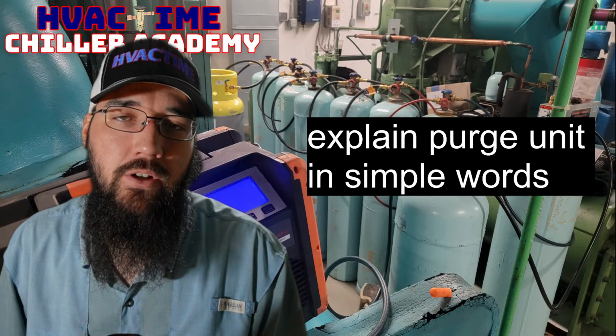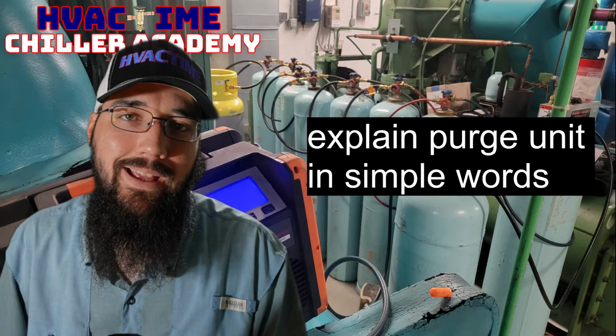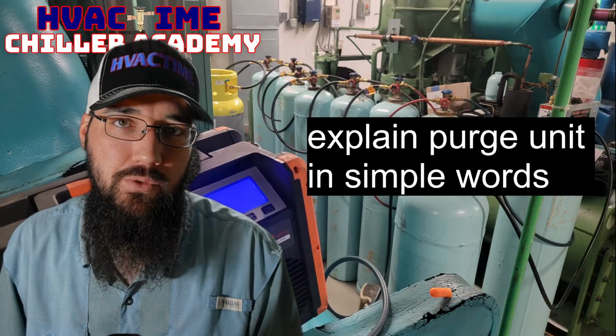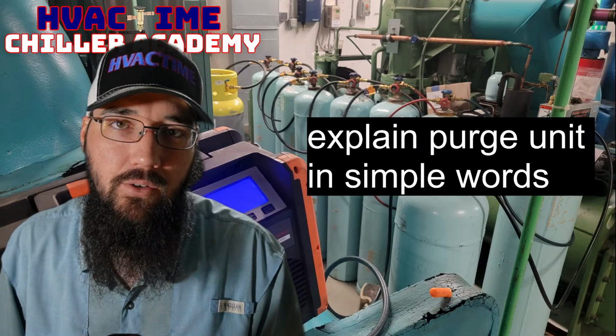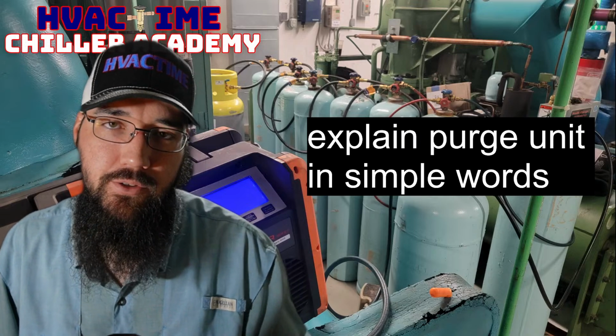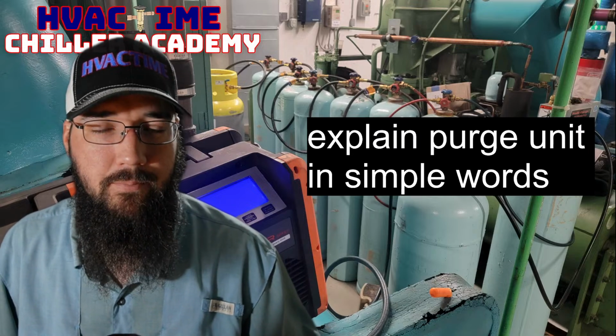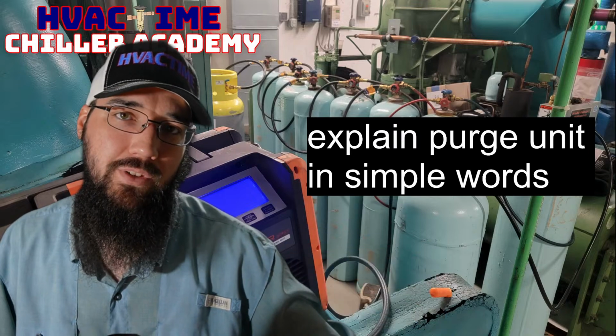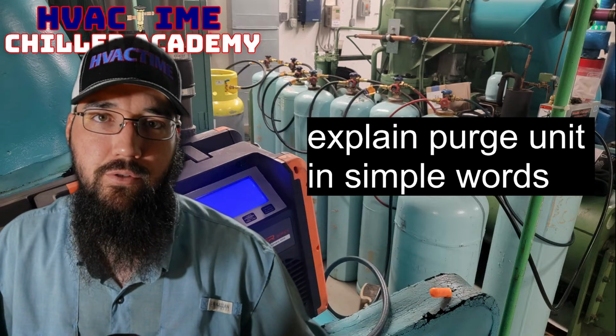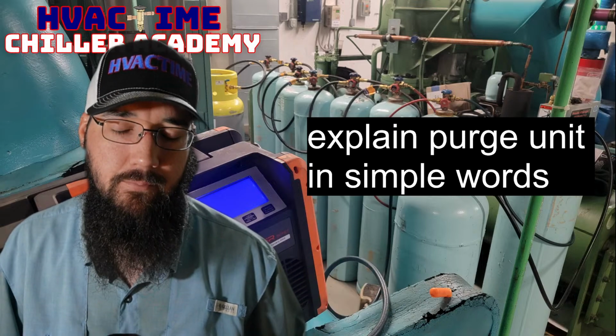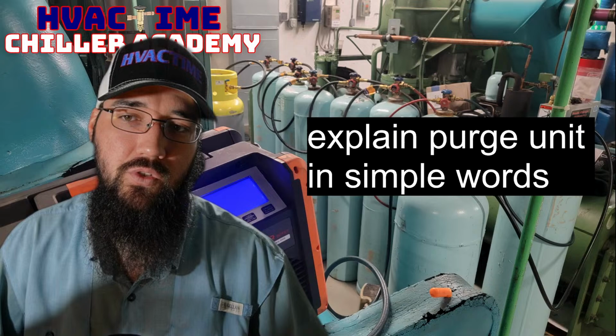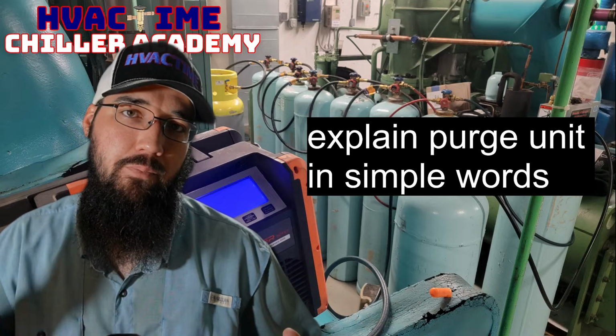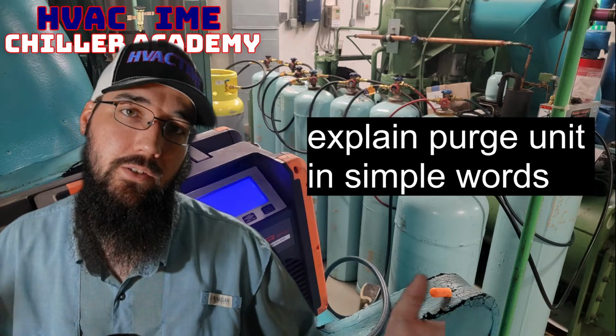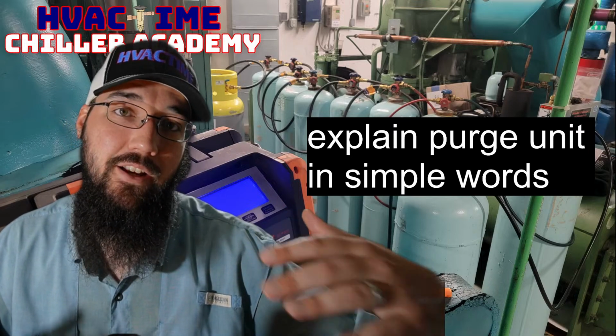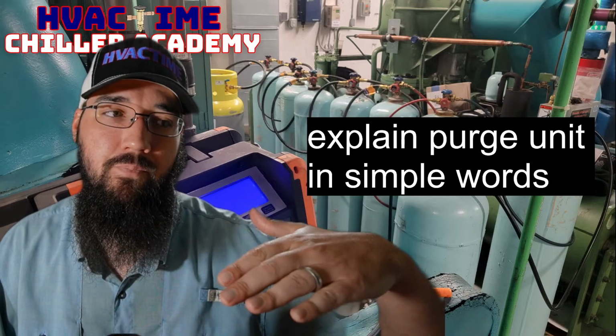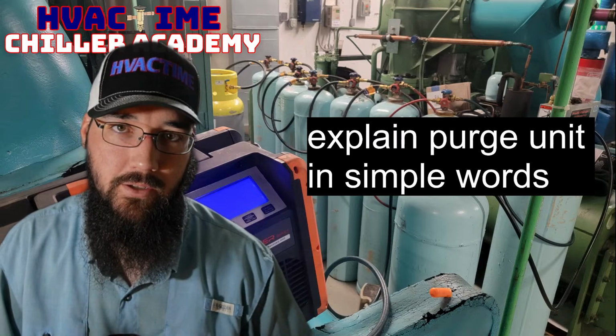A purge unit is on a low pressure machine. It is used to remove non-condensables of whatever kind out of the chiller. With low pressure, we operate in a vacuum below atmosphere. Non-condensables can get in through just general leaks, right? However they get in, the purge is able to separate those. It separates them by making the refrigerant condense, because it is a condensable. And the non-condensables, whether it be moisture or air, won't condense because they're non-condensable, right?